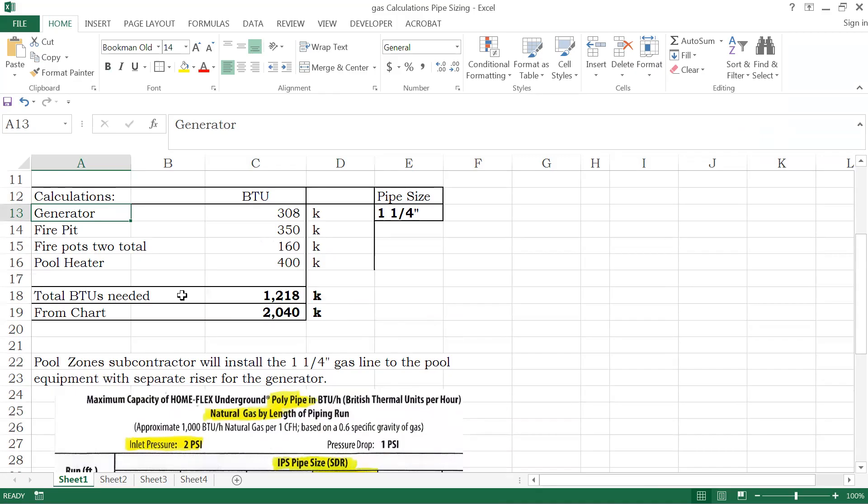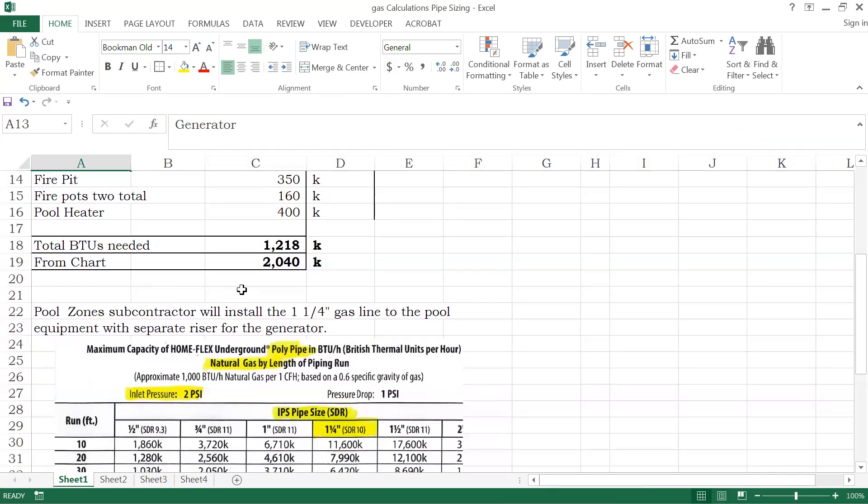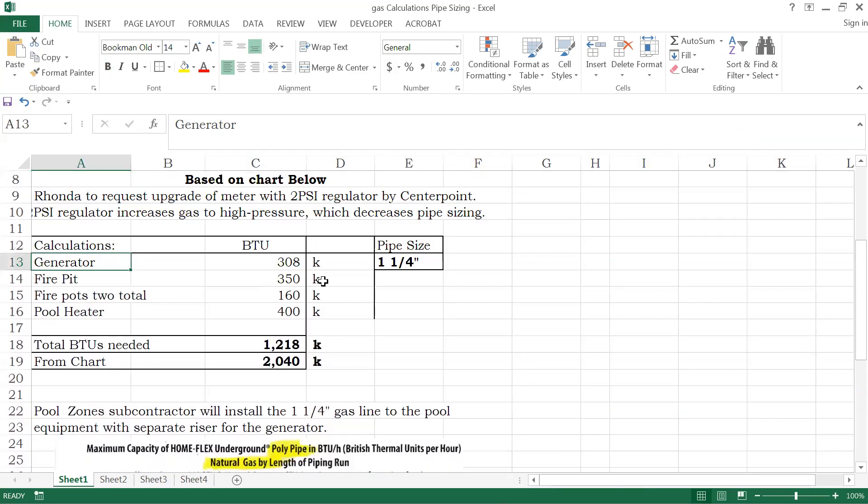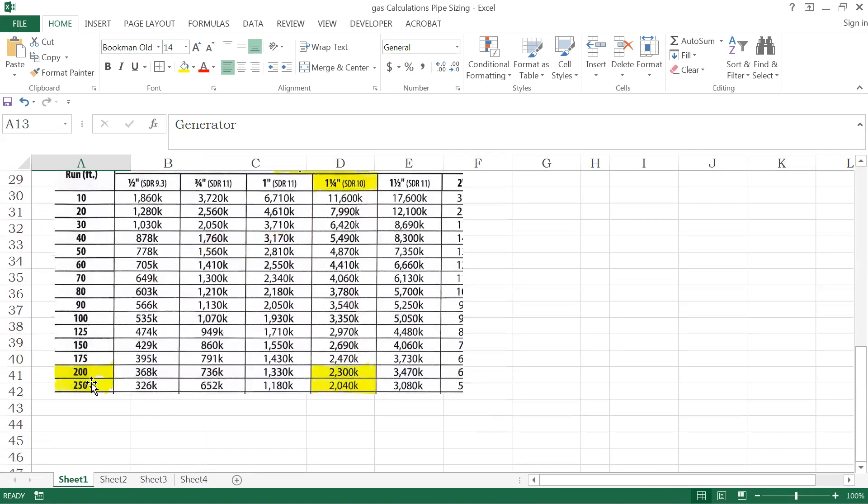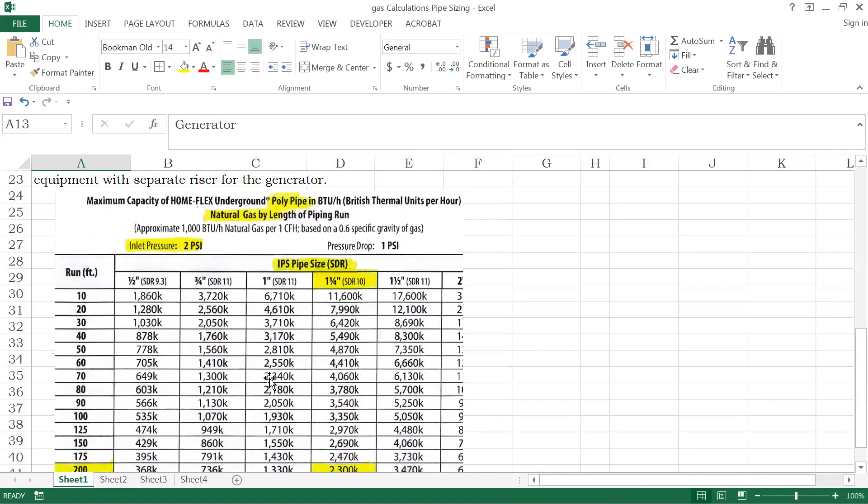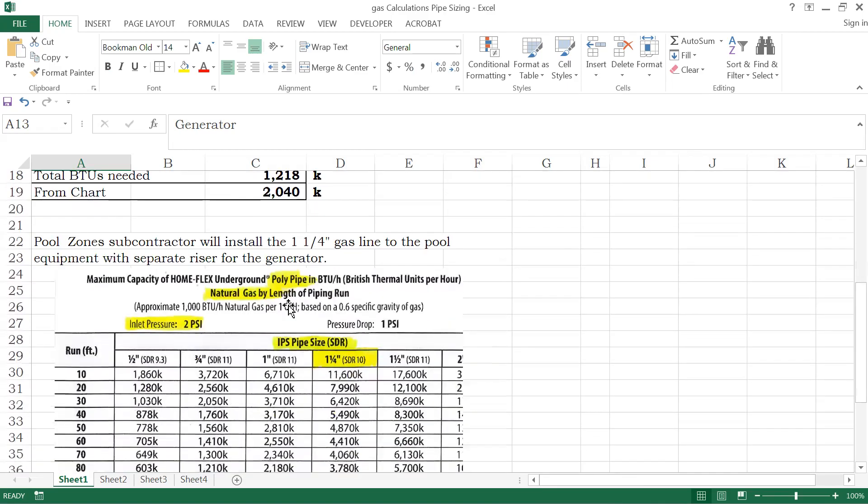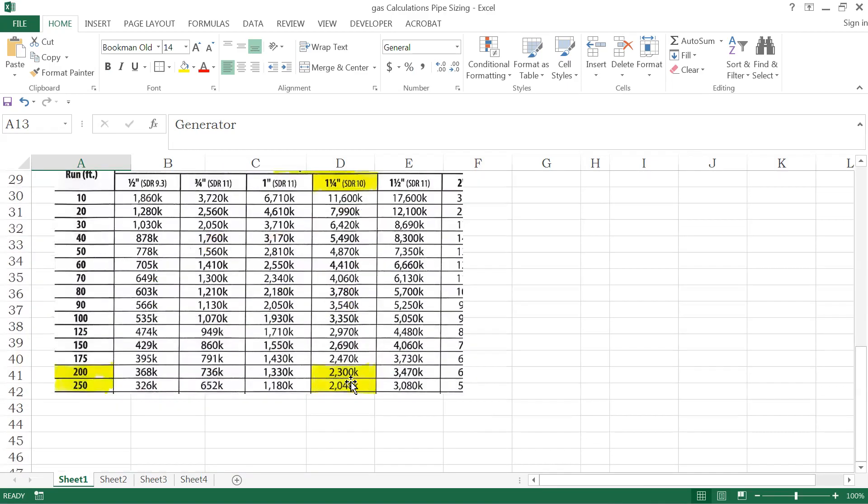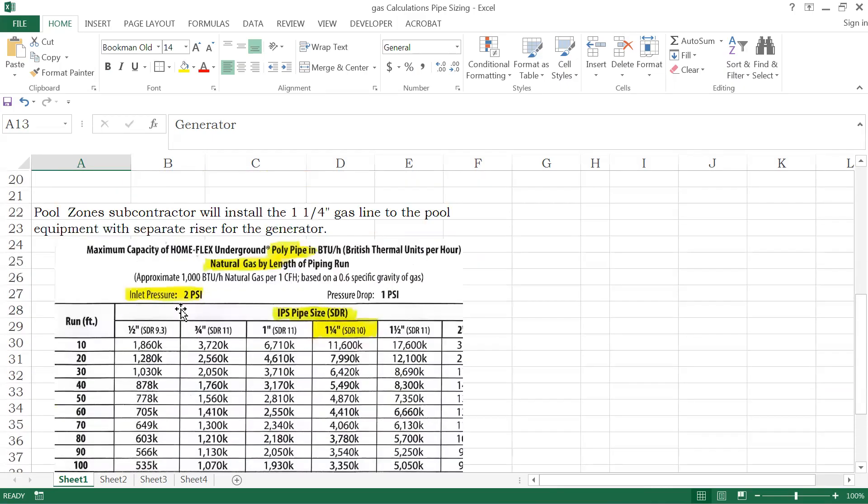From the chart we can see that basically what I need is, if I'm running 200 to 250 feet, I'm going to want to make sure I have plenty of gas. I'm aiming for one and a quarter inches because if I step it down to one inch I'm too close to what I need. Sizing it up a quarter inch gets me a lot more gas than I need and that's typically where I want to aim.